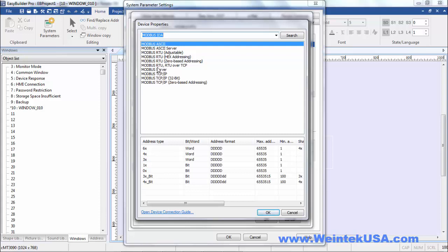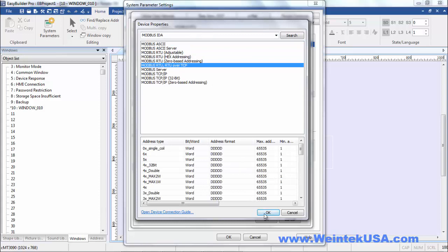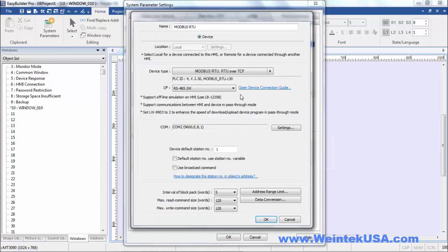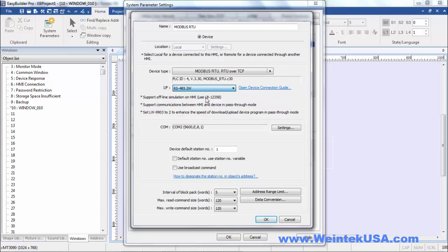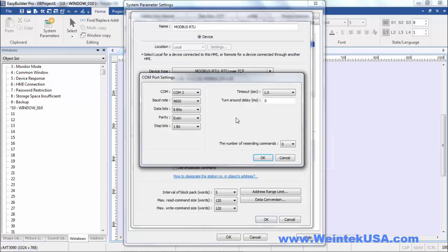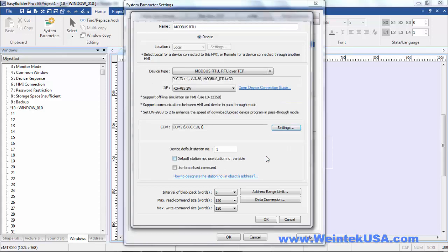So if we're going to look at a serial driver, here we want to select the serial protocol that we want to use within Modbus. I'm going to select RS-485 two-wire. Under the settings, you select the actual serial properties that you need to set to match your device. We've got a timeout that you can set for a maximum time without communications before it gives an indicator. You'll get a PLC no response. And then you can also define a turnaround delay to allow time for bus traffic.